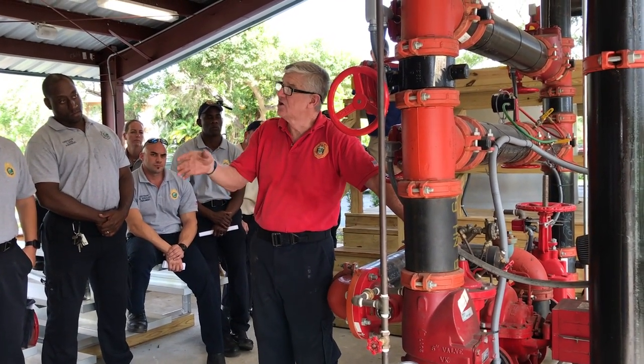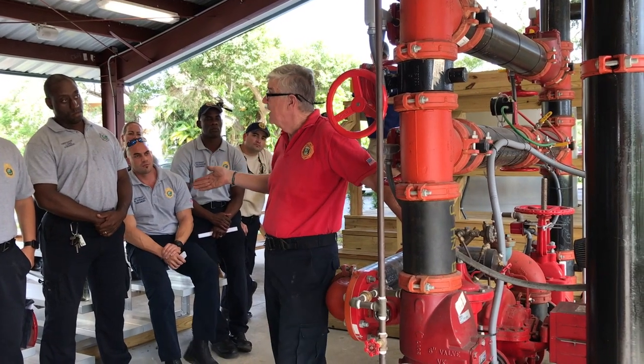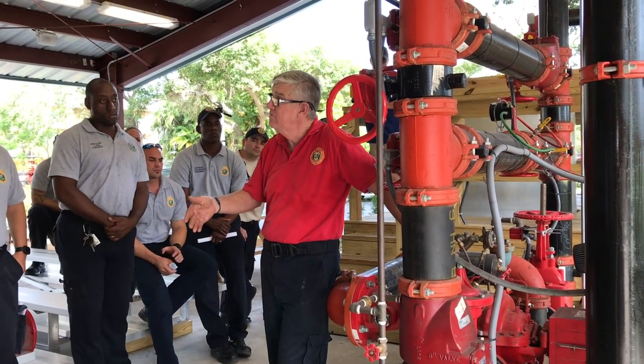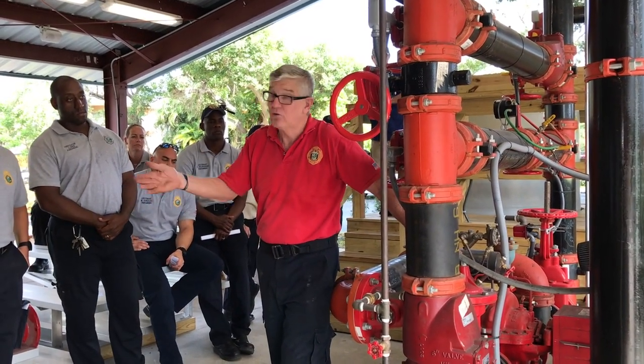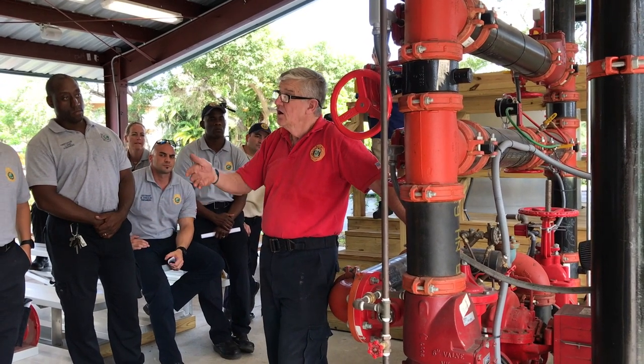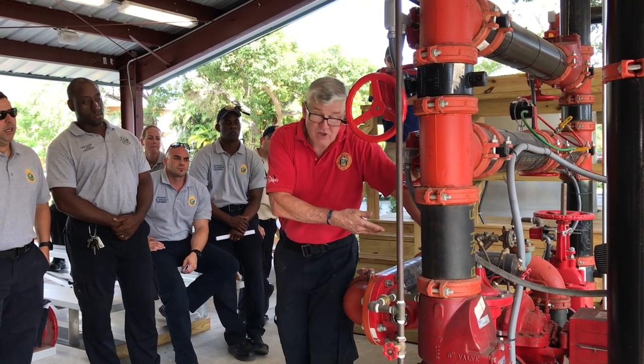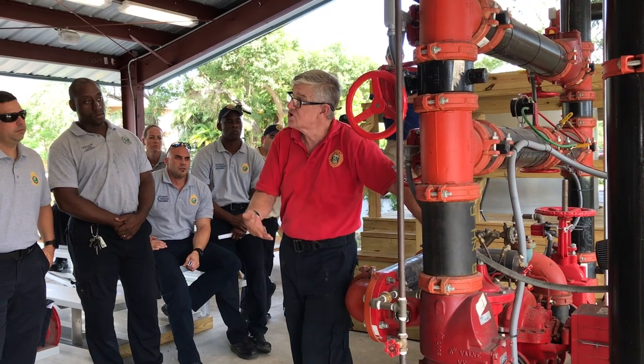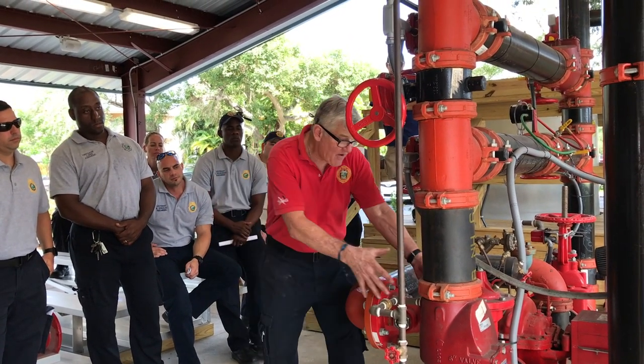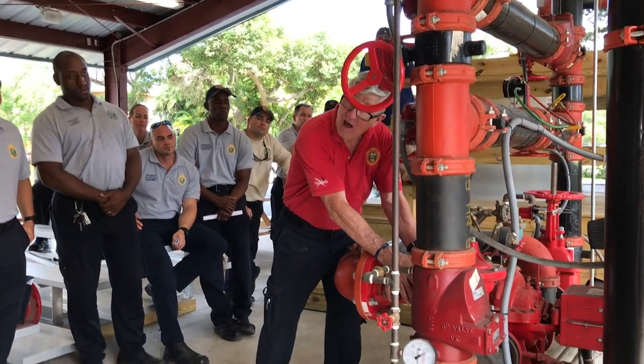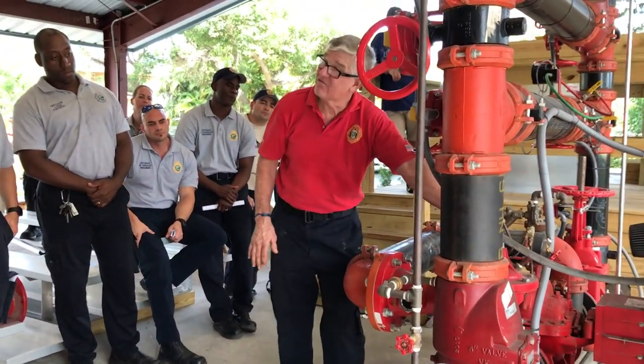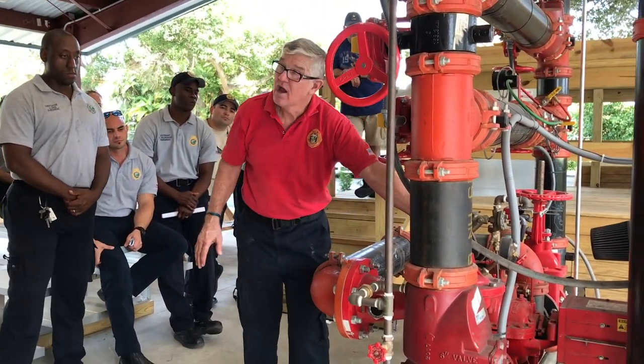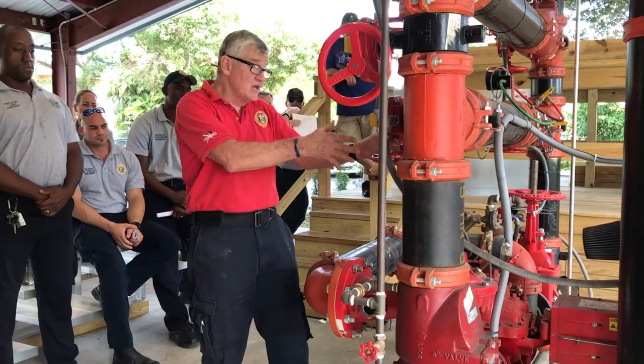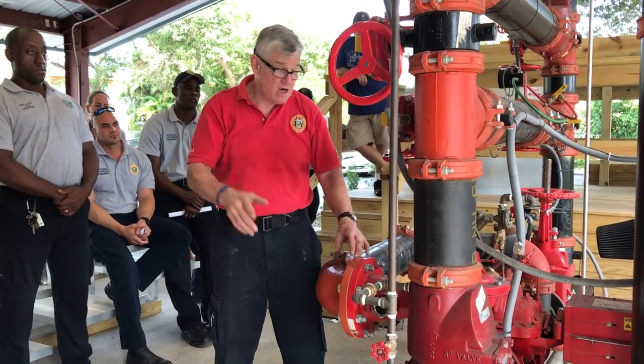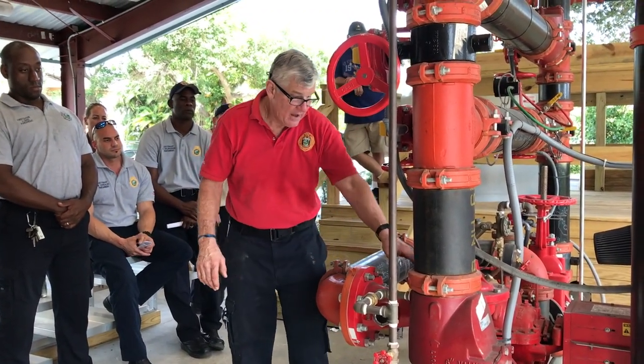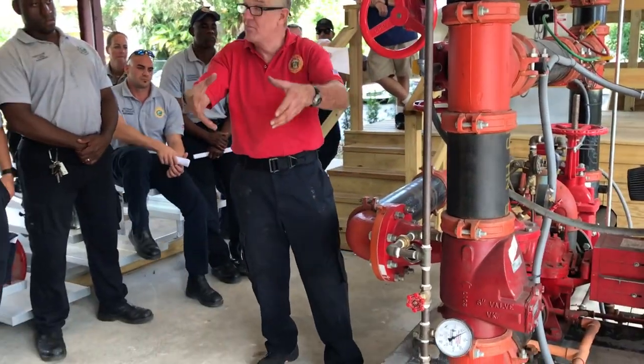Diesel engines occasionally, and I think you've seen it in motor vehicle accidents, where a diesel engine will run wild, over speed. If it overspeeds, what's going to happen to the pressure in this pipe? You're going to burst the system. So you have a very large relief valve controlled by this pilot valve assembly adjusted here. In case the diesel engine should overspeed to control the pressure, the very large relief valve dumps a lot of water.